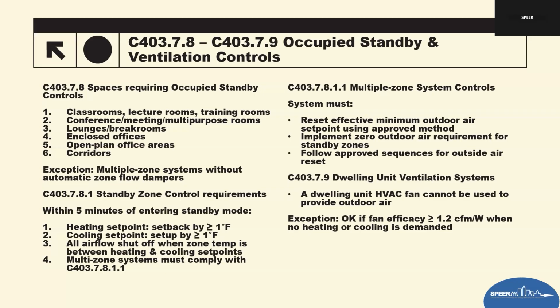These standby controls significantly reduce energy waste by cutting airflow, reducing mechanical heating and cooling, and lowering outdoor air demand when rooms are unoccupied. So all without compromising comfort when the space becomes occupied again. Plan review tips. Confirm occupant sensors, the types, and the control sequences. Verify airflow shutoff capability, so zone dampers are required. Check outdoor air reset logic for multi-zones. And then verify dwelling unit ventilation systems meet fan efficacy requirements.